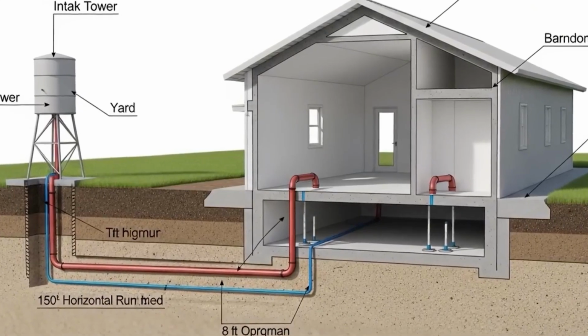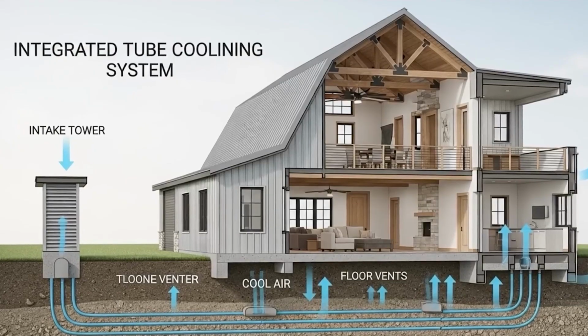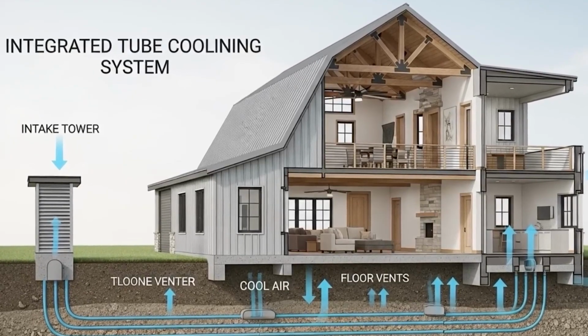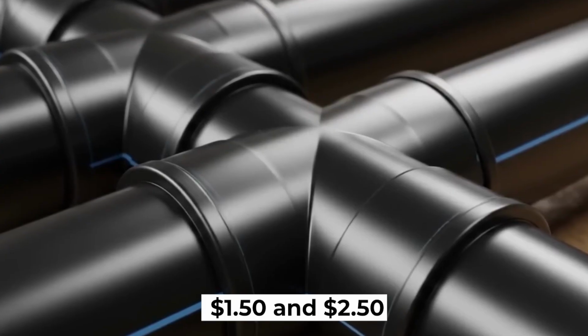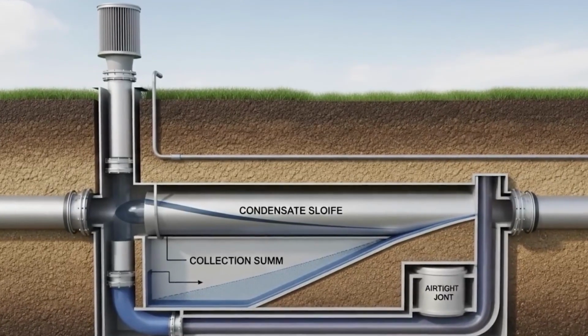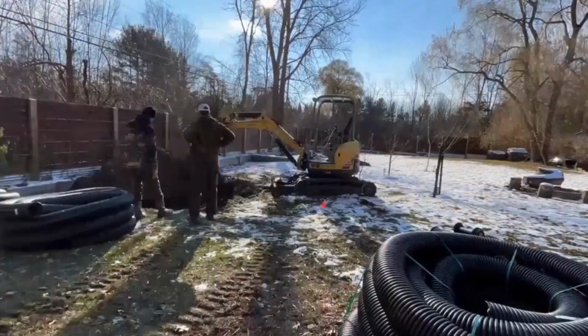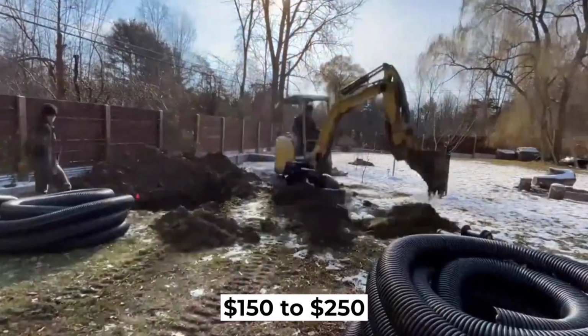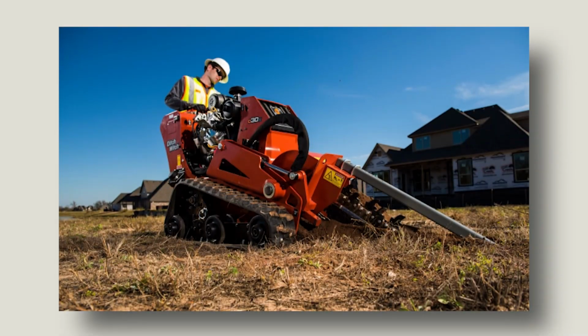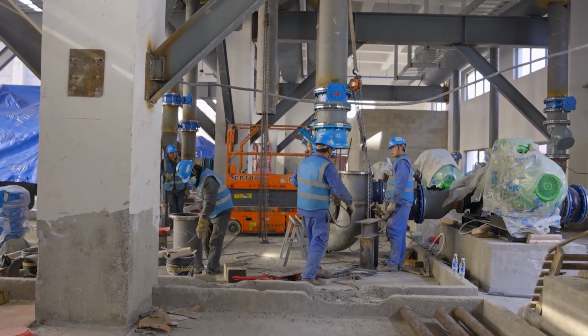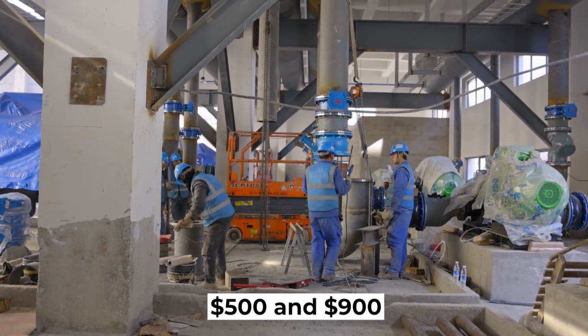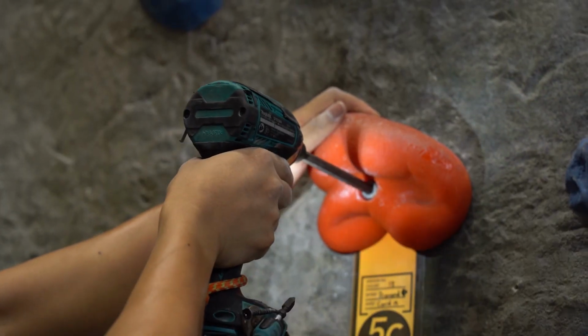At the building entry point, a bypass damper lets you switch between earth tube cooled air in summer and direct outside air in winter, preventing the system from drawing cool ground temperature air into the home when you want warmth. The pipe itself costs between $1.50 and $2.50 per linear foot for 6-inch HDPE, putting materials for a 100-foot run at roughly $150 to $250. Excavation with a rented walk-behind trencher adds between $200 and $400 for a half-day rental. Fittings, inlet cap, filter housing, and damper bring the total to between $500 and $900 for a careful DIY installation.